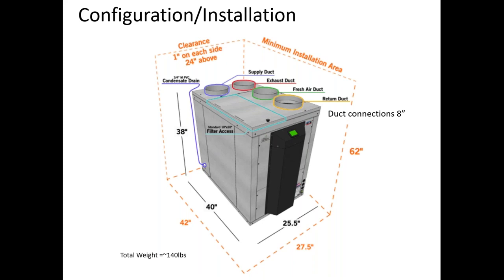It needs to go into conditioned space. It doesn't have to be fully conditioned, but roughly 50 to 85 or so degrees, just to maintain good efficiency and operation of the system. Outside that range, you can run into trouble, especially with condensate at low temperatures that can lead to freeze up. So you just want to make sure that the space is adequate for that.